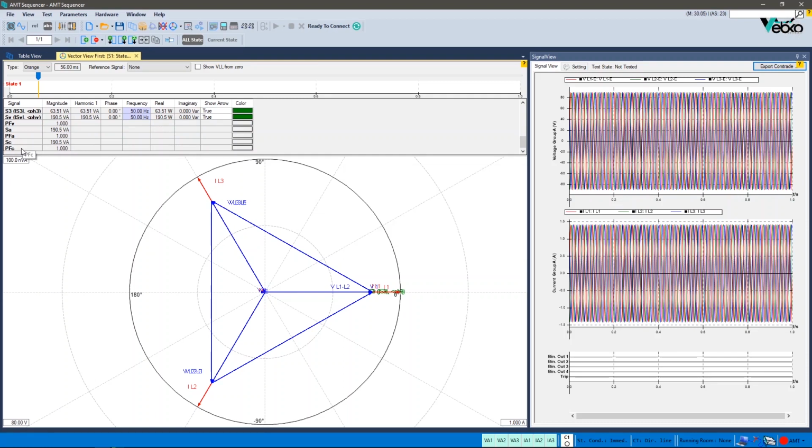You should keep in mind that S1, S2, and S3 quantities are the same in all 3 methods and displayed on the vector. Also, when the load is unbalanced, the Power SC method works better than the others, and sigma V and sigma I parameters refer to the algebraic sum of voltages and the algebraic sum of currents, respectively. Also, V and I parameters refer to current and voltage of the system, which are calculated in a 3-phase system using the displayed formulas.